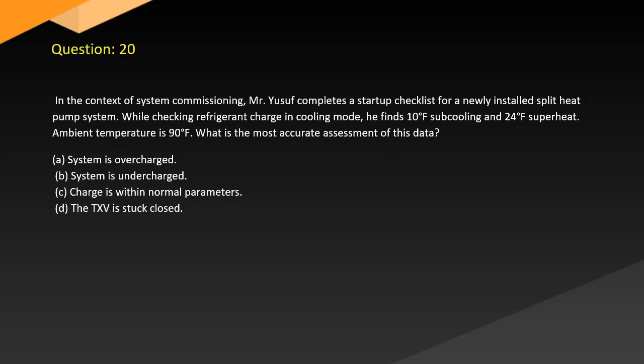Question 20. In the context of system commissioning, Mr. Yusuf completes a startup checklist for a newly installed split heat pump system. While checking refrigerant charge in cooling mode, he finds 10 degrees subcooling and 24 degrees superheat. Ambient temperature is 90 degrees. What is the most accurate assessment of this data? A. System is overcharged. B. System is undercharged. C. Charge is within normal parameters. D. The TXV is stuck closed.